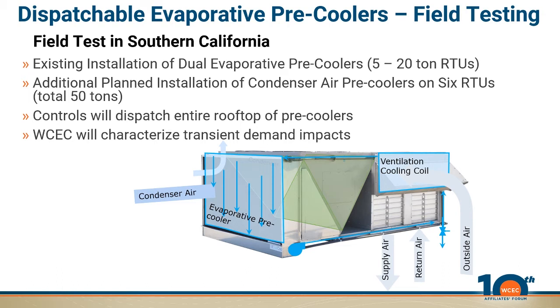If we're talking about peak, it depends upon sizing and where you are with your load. So what's being asked is whether the field test should capture the effect on COP, not just the impact on power draw. In other words, when I turn on the water, the electrical demand goes down, but the capacity goes up. You should see the effect of that capacity increase if the equipment is turning off. But if it's running flat out, you won't see it. If it's sized correctly for that load, you should see it.